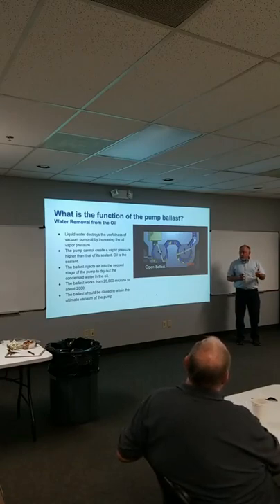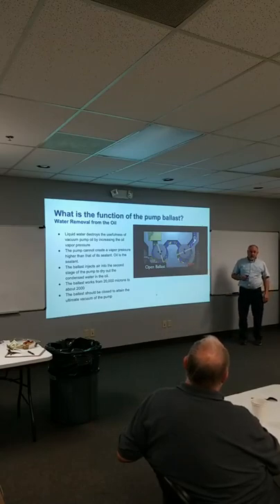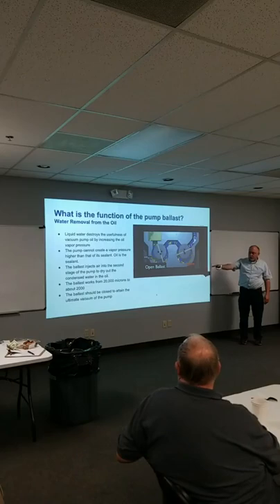Now, if you're using true blue hoses, you're gonna blow past that really fast. But if you're on a wet system, literally it'll come down on a flat line like this, okay? And in flat lines, you wanna open up that ballast and let it help remove the moisture from the system. Otherwise, it's gonna emulsify in your oil and the vacuum's gonna stop. So the ballast works from about 20,000 microns down to about 2,000. At 2,000, you shut it off because you don't need it anymore, okay? It should be closed to attain the ultimate vacuum of the pump.